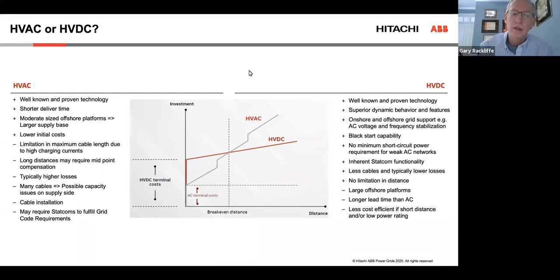The charging current associated with that capacitance then increases if you have an AC cable. When you have a DC cable, you don't have that charging current. And that's why the losses are lower for high voltage DC cables. And there's really no distance limitation for a high voltage DC cable. With high voltage AC cables, you do have that concern over long distances that you are going to have higher losses unless you provide some type of compensation.